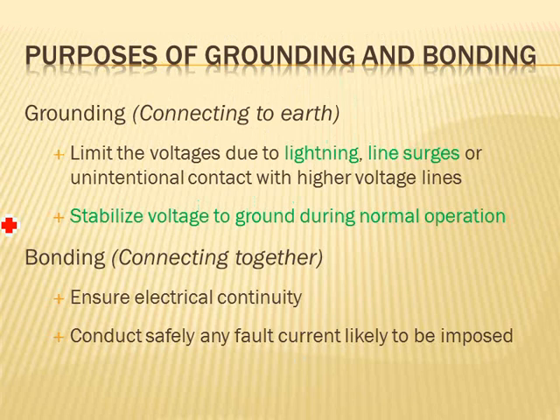Okay, purpose of grounding and bonding. A couple of things, guys, you are familiar with that. Limit the voltage due to lightning, line surges, or unintentional contact. I don't know how many people pay attention to this. Stabilize the voltage to ground during normal operation. Now, grounding the system. Why do I care about taking the negative in the 9 volt, tying it to the ground as I power that bulb that's tied to it? 9 volts is not a whole lot, but in a higher system, the most important thing when we tie it to the ground is that we stabilize the voltage to the ground.